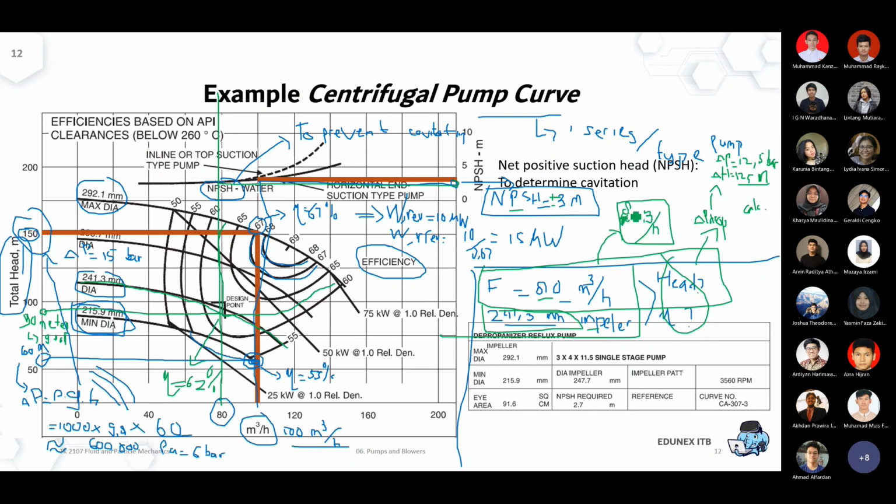Okay, I changed my mind, so that you don't really have a lot to extrapolate. Instead of 60, let's say you have to transfer 85 cubic meter per hour of gasoline or diesel. Okay, you know your head requirement is 12.5 meter, and then you know that your flow rate capacity is 85 cubic meter per hour. Is it doable to transfer this oil using this pump?